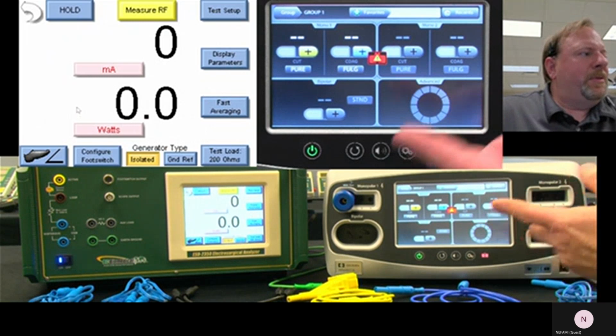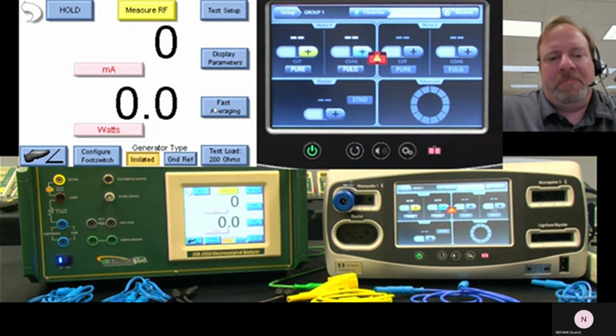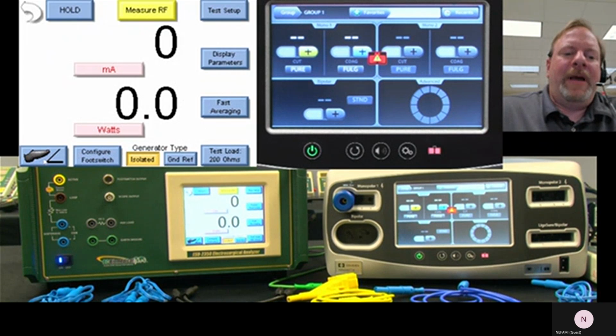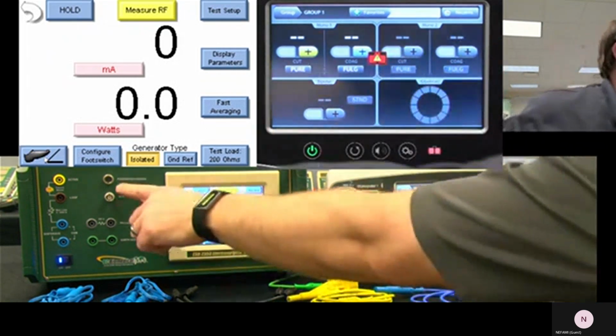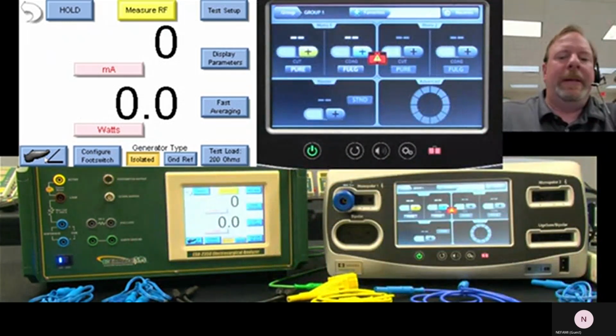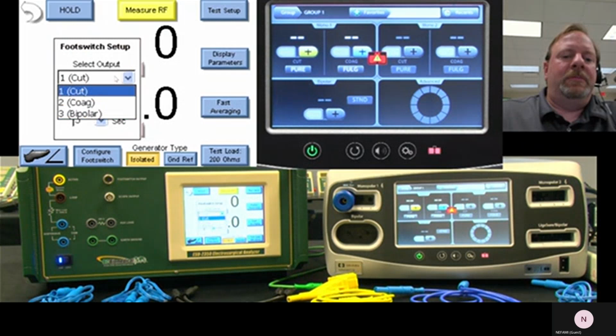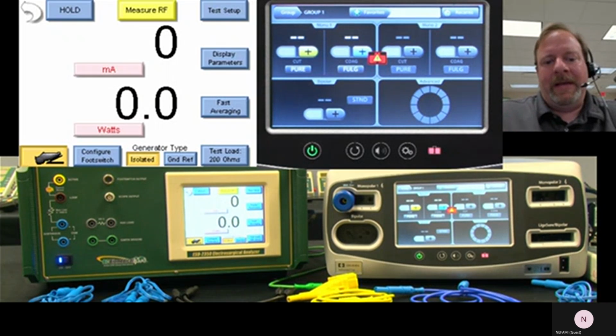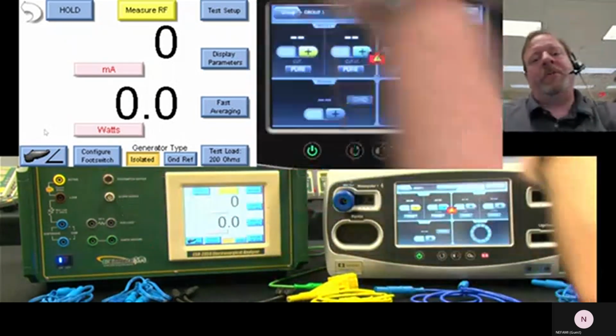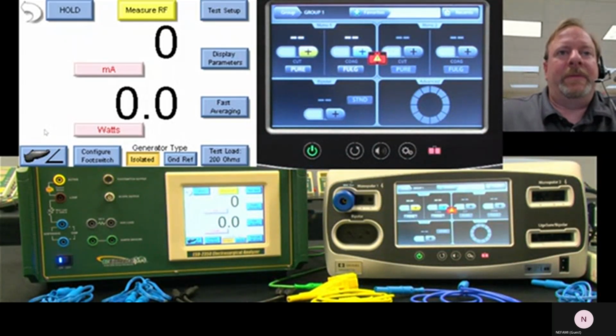And for the most part, with this 2350, you can leave it in fast or medium, and the measurement won't bounce around too much for you. It'll be nice and steady. Down in the bottom row here, we've got our foot switch. So this actually activates the foot switch output here, allowing you to trigger your generator. And then we can select which output we want to use, how long we want it to be active, and then when we hit that button, it will activate that. It's meant to interface between our foot switch output port and your generator for the Force FX, Force Triad, FT10, that sort of thing, ConMed. There's a bunch out there.